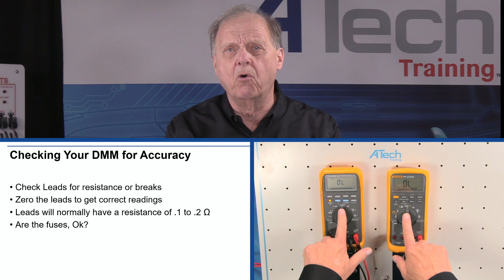You always want to make sure you're using the lead setup with the best connection. Now notice, I've got 0.1 showing. If I wanted to get rid of that and zero out the leads, I'd hit relative on this unit - it would take that reading out. Let's hit it again - there we go, it takes the reading out and brings me back to zero. Now if I go to my other meter over here, it's a little different. Every meter is slightly different, so for this one I'm going to hold the leads together.